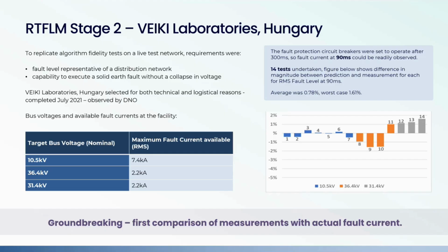Again, we learned an awful lot from this. So there's some things which are impossible to predict. So, for example, if the poles of a circuit breaker don't close at precisely the same time, and they're slightly asynchronous, then that could actually affect the end value of the fault current. So it's impossible to get an absolutely perfect comparison, because there's physical limitations in terms of what we can predict in the network. But nevertheless, as you can see, we're extremely pleased with the comparison of results there. We go to the next slide.